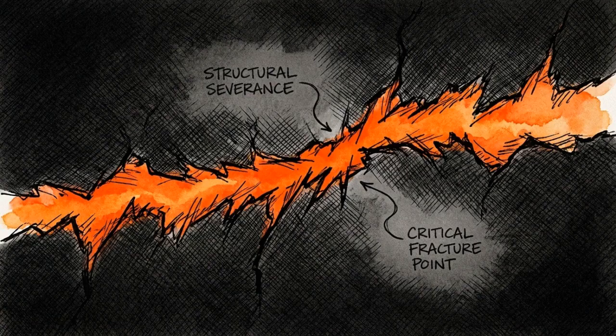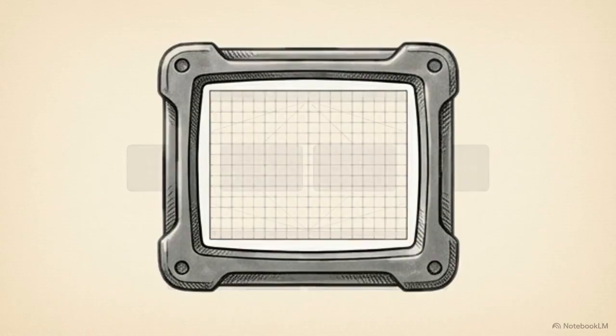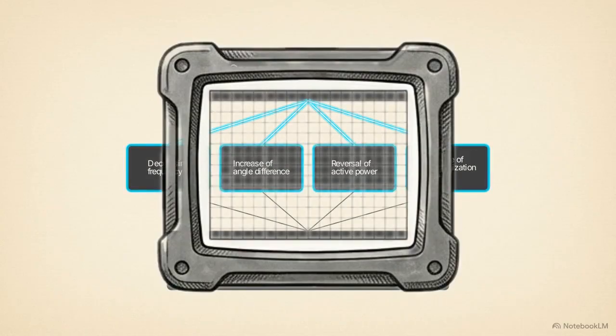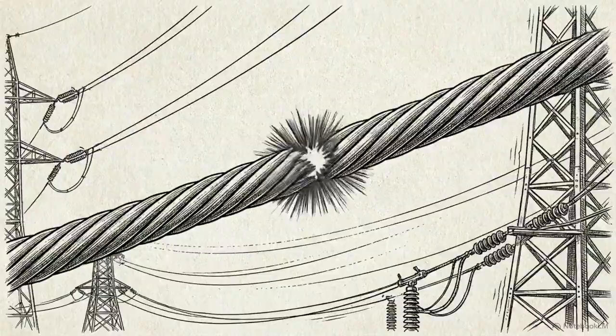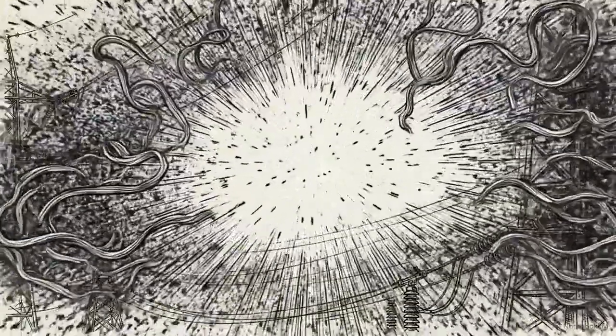At 12:33 and 19 seconds, the cascade of disconnections crossed a critical mathematical threshold, stripping the Iberian system of its required synchronizing torque. Mapping this back to the autopsy framework, the cascade lands exactly on this node, the point of no return. The critical AC connection between the Iberian Peninsula and the rest of continental Europe violently severs. The physical consequence of this break is that the Iberian transmission angle diverged so drastically from continental Europe that it triggered the out-of-step protection relays at the French border, severing the physical lines.